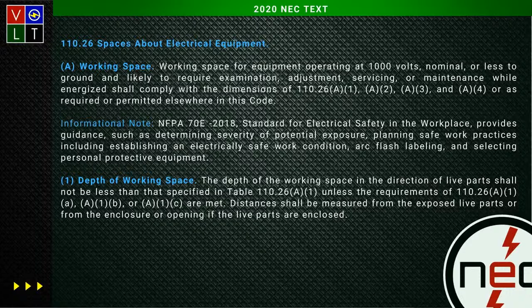Now this is just showing, say I'm in condition 1 and I have a 277/480 volt system there. So we're at 277, condition 1—what's my clearance in front of the equipment? I'd say 3'6". I'm in condition 1, not condition 2. Oh okay, 3 foot. Yeah, anything in condition 1 is always 3 foot.